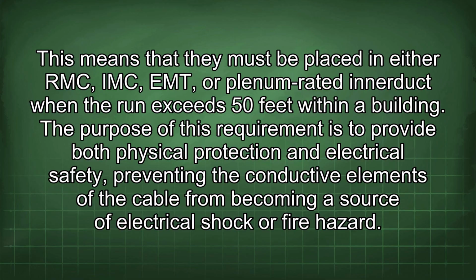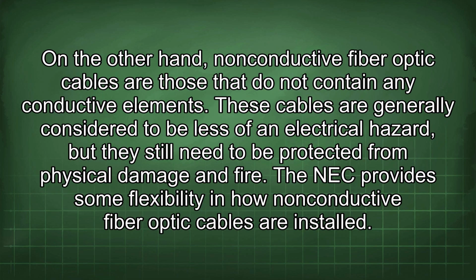The purpose of this requirement is to provide both physical protection and electrical safety, preventing the conductive elements of the cable from becoming a source of electrical shock or fire hazard. On the other hand, non-conductive fiber optic cables are those that do not contain any conductive elements. These cables are generally considered to be less of an electrical hazard, but they still need to be protected from physical damage and fire. The NEC provides some flexibility in how non-conductive fiber optic cables are installed.